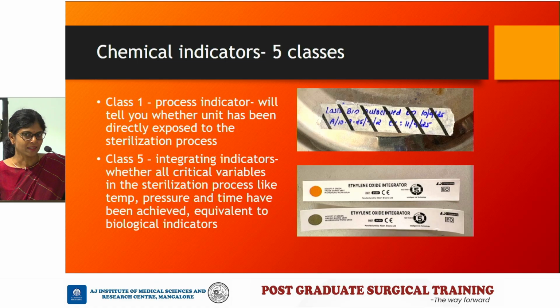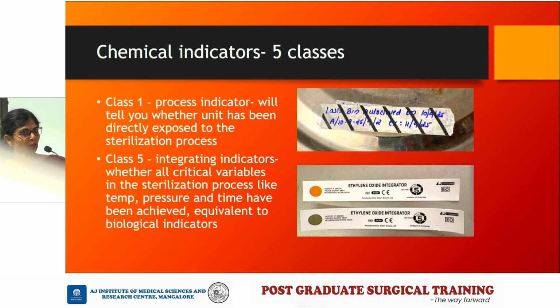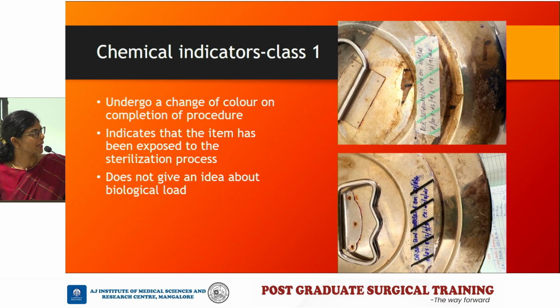Coming to chemical indicators. Now this is what you generally see on the bins. So the chemical indicators are of 5 classes, but what we generally use are the class 1 and the class 5 indicators. Now class 1 is a process indicator. It will only tell you whether the unit has been exposed to the sterilization process, nothing else. Whereas a class 5 indicator will tell you whether all the variables like temperature, pressure, time have been achieved, and they can be counted equivalent to biological indicators, which are the gold standard of sterilization. So this is a class 1 indicator. You can see on the top picture that it is not yet done, and then there is a color change down, so it is done.